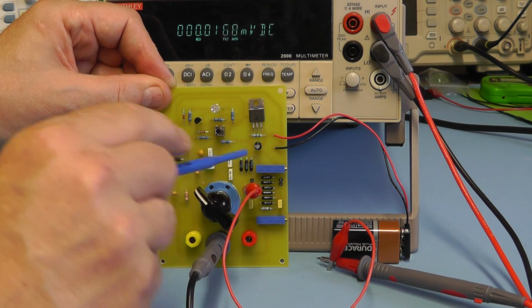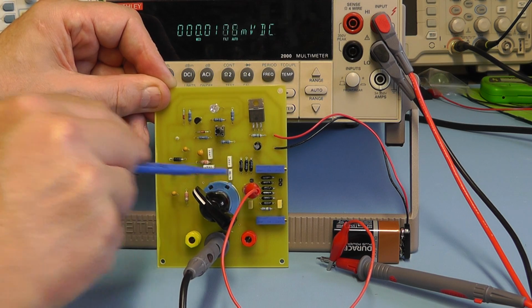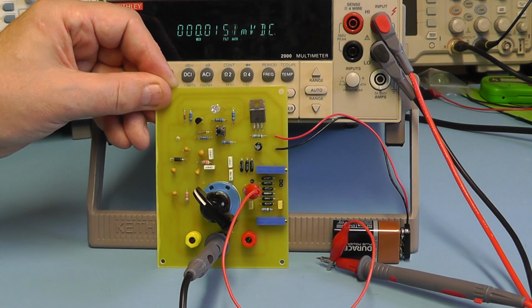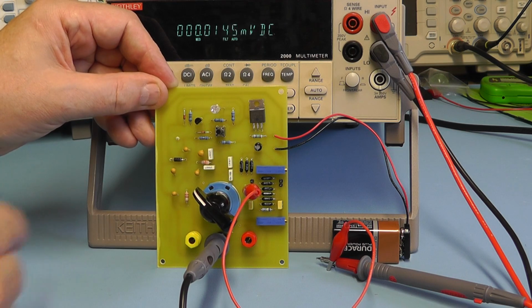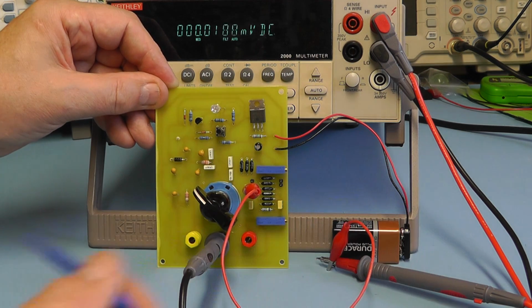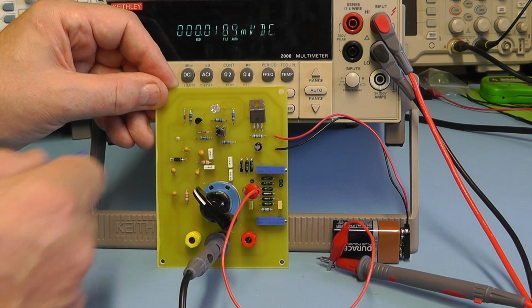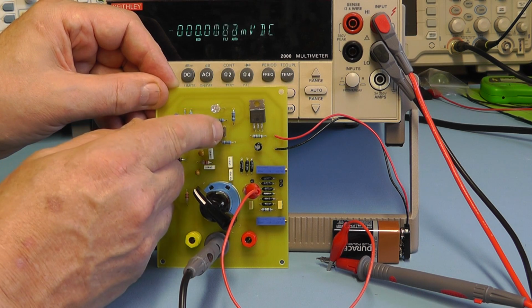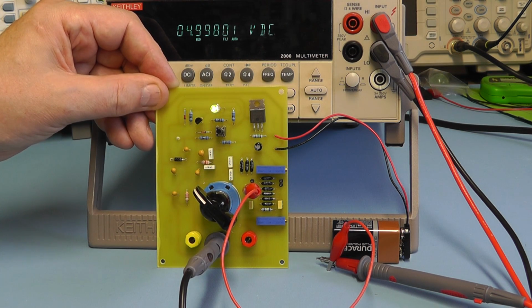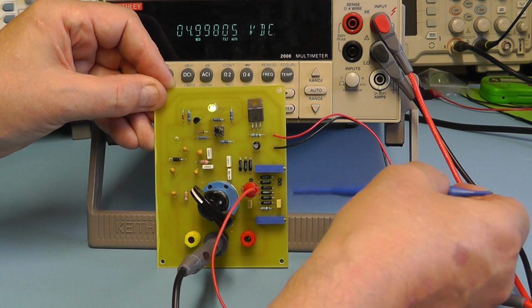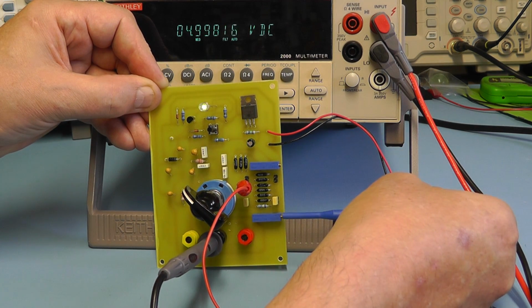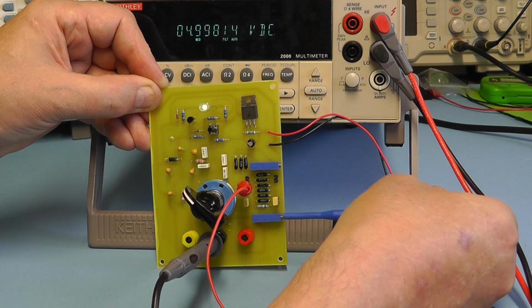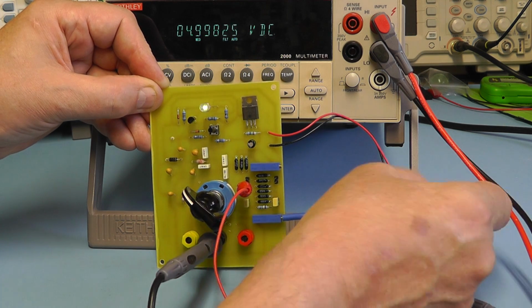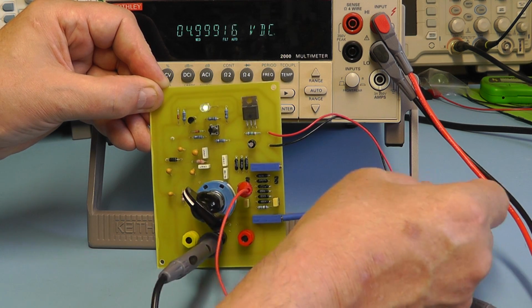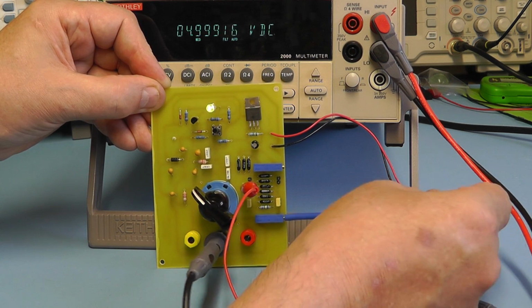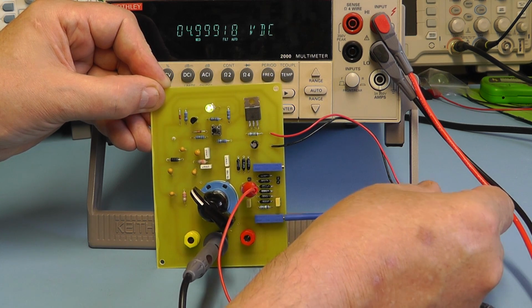I have the positive of the meter lead going to the calibration point for the 100 millivolt calibration setting, and I'm now going to switch on and trim the preset and try and get half of that 10 volt reference that we had. So let's switch on. So it's reading low, that. So let's see what we can do now and try and trim that. It's coming up. Try and get it to... Right, that's as far as I can get it.